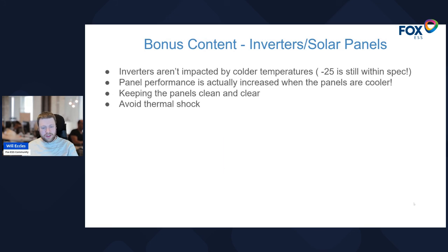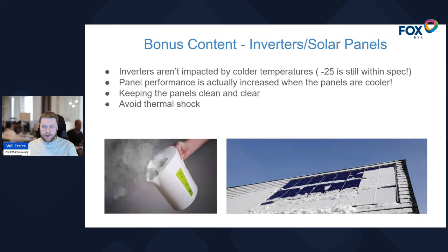Avoid thermal shock, this works both ways. In the summer, I will clean my panels on a cooler morning before the sun comes up. I won't look at them in the afternoon in the peak heat of a July afternoon and think I could do with cleaning these panels, because I don't want to risk damaging them through thermal shock. When the panels are colder, they're also more sensitive, so keep that in mind if you're thinking about buying a brush extension and cleaning the panels yourself. You want to do it not when it's freezing cold, not when it's boiling hot, but on a pretty mild day where the sun isn't out and they're not having to work hard and perform.